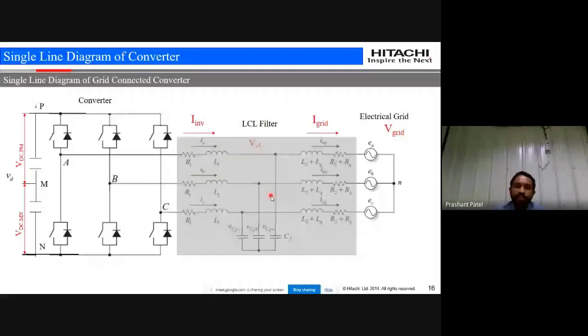According to our requirement, we can select whether to use an L filter, LC filter, or LCL filter. Also, instead of an inductor, we can select a transformer — either an auto transformer or an isolation transformer. If the customer wants isolation for the converter, we use an isolation transformer. If they don't want isolation, an auto transformer is preferable, since using an auto transformer instead of an isolation transformer gives an advantage in cost.